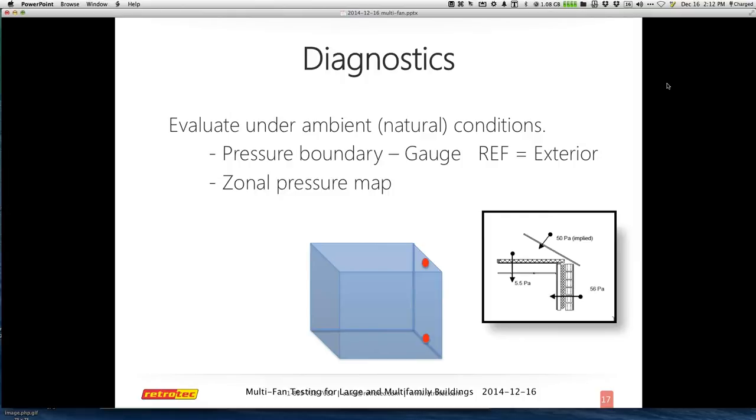I edited an article for Retrotec last week that will be in the NEB mailer, which talks about really starting with ambient conditions. You just go around with your gauge and some tubing connected to the outside and evaluate how connected the units are, what type of stack effect you're reading, where the stairs are, what's inside versus outside. You can map out a lot about how the building functions under normal conditions with just a gauge and a variety of long tubes reaching other parts of the building.